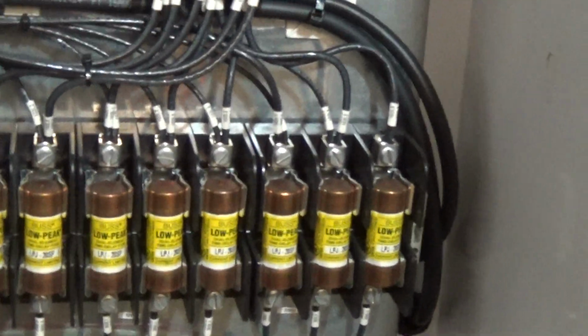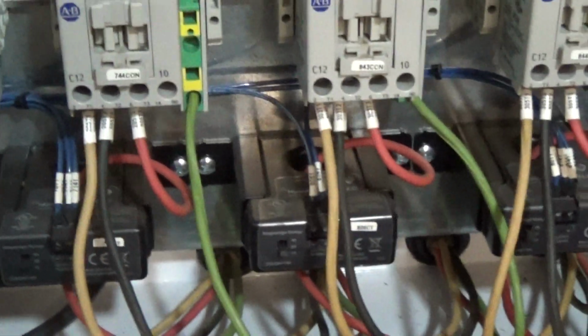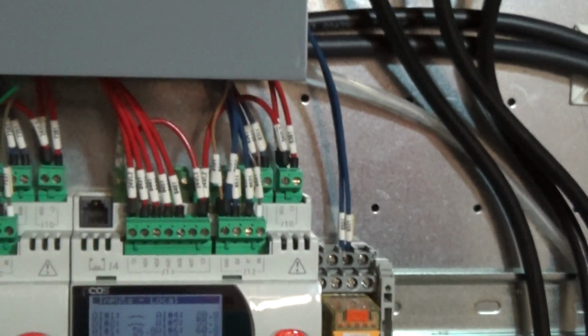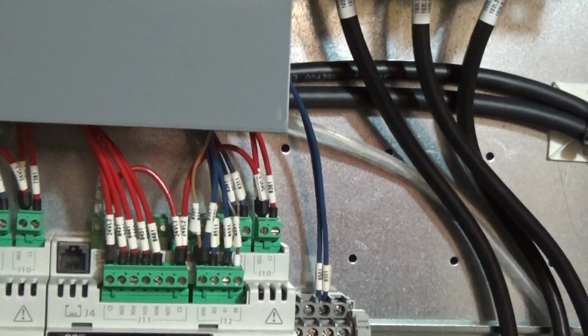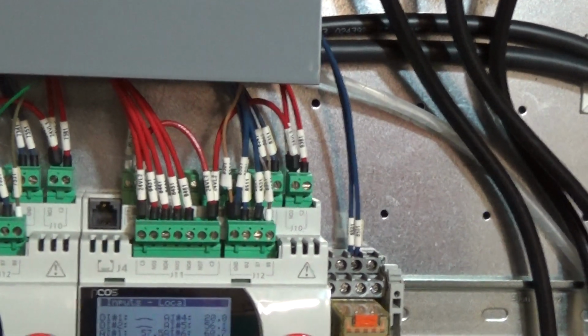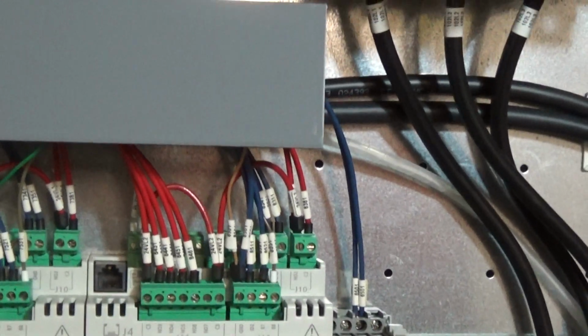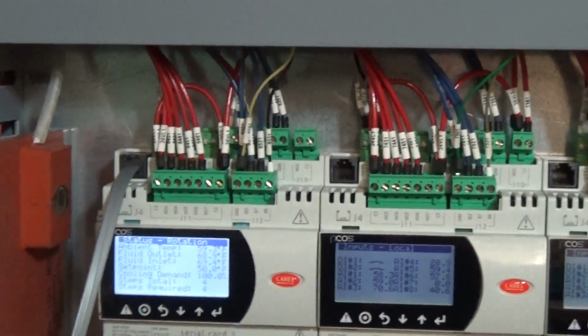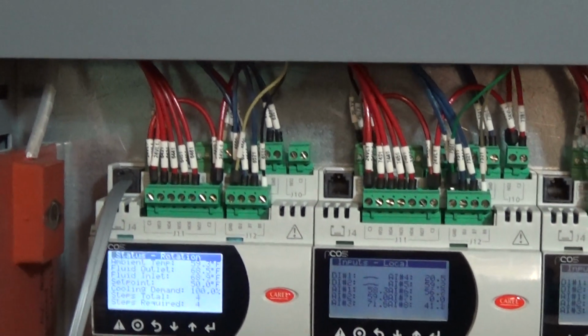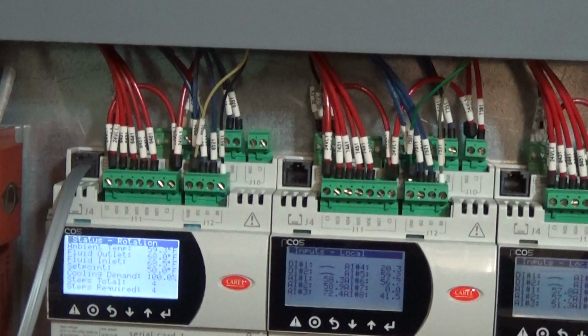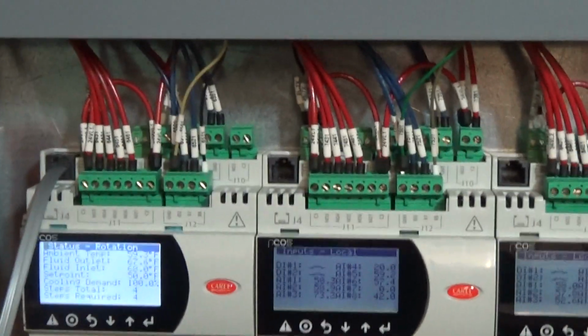You can see I've got all 4 contactors pulled in, so I'm running full 100% cooling. Just under those are current transducers that monitor the compressor amperage. That's one of the signals that gets fed back up to the 2 auxiliary PLCs, besides your temperature sensors and your pressure transducers that are in the fluid loop and the refrigerant loop. So what this will do is it runs the 4 different stages as it needs to for cooling. And it will try to balance off the hours on each machine. So the first one on would be the first one off. And it tries to rotate which one runs depending on the load.